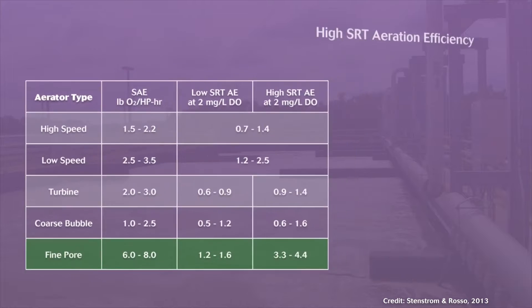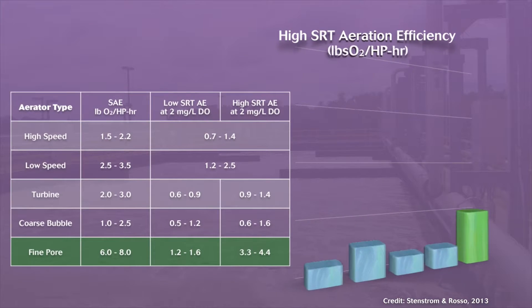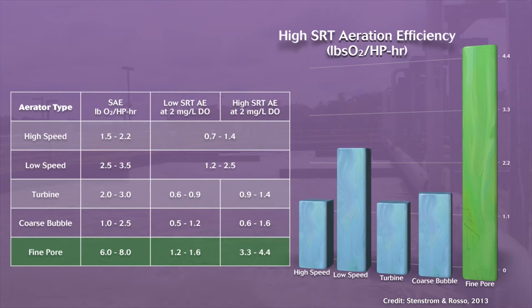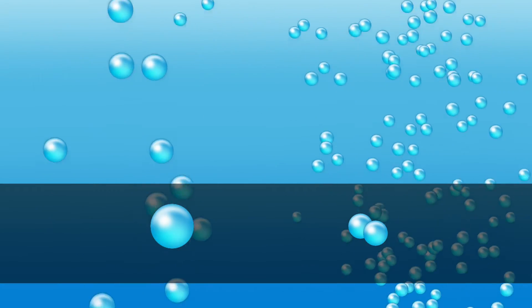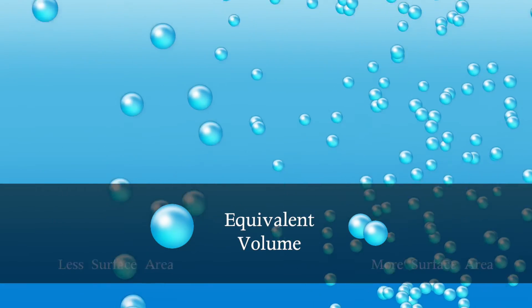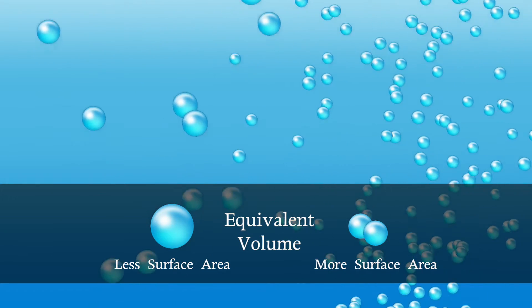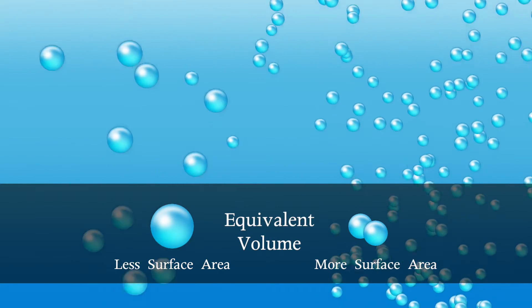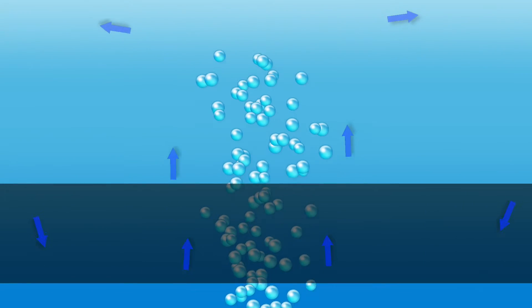Because fine pore diffusers are generally the most energy efficient aeration system, they are also the most common system in use today. The efficiency of fine pore diffusers comes from two basic principles: first, the formation of small bubbles which have a greater surface area relative to the volume of air inside the bubble, available for oxygen transfer across the bubble membrane; and second, the maximizing of bubble retention time in the tank through the reduction of convection currents.